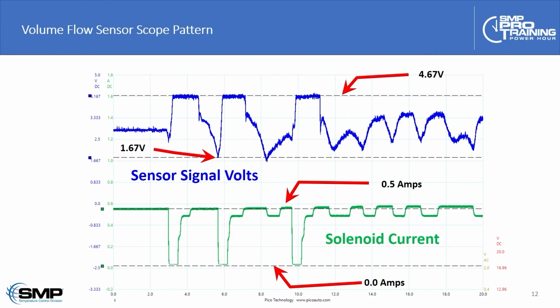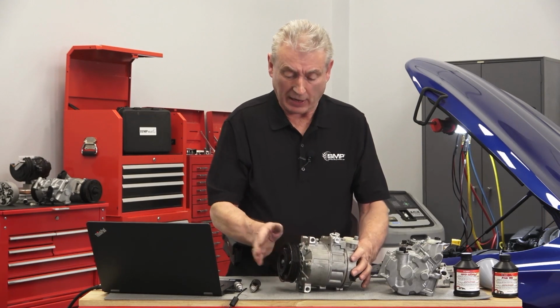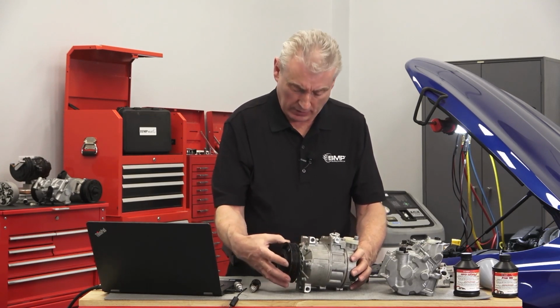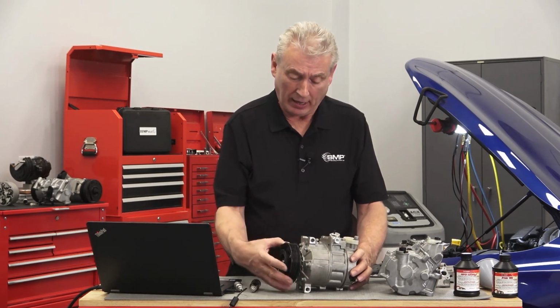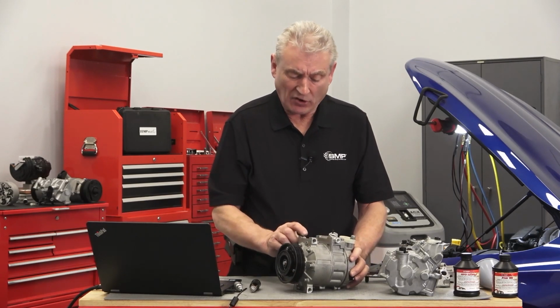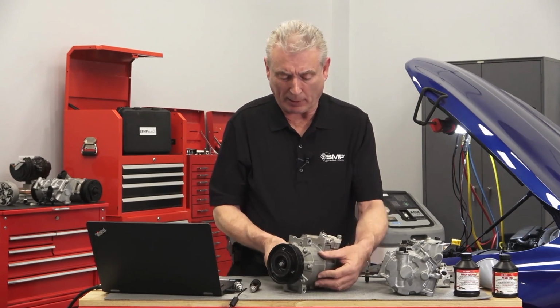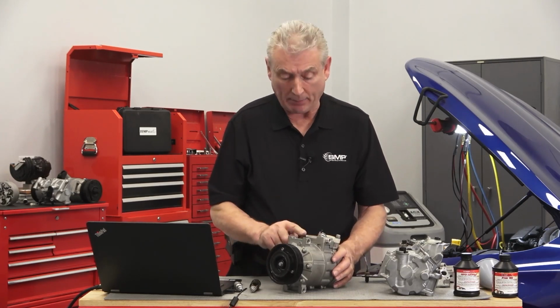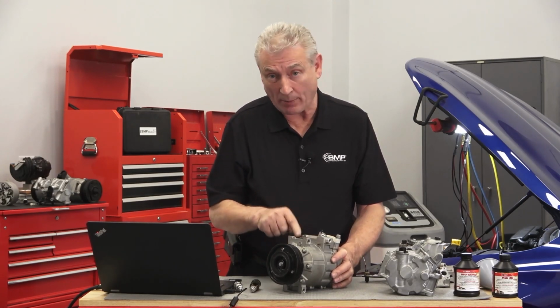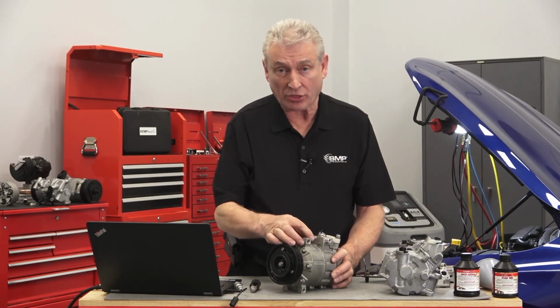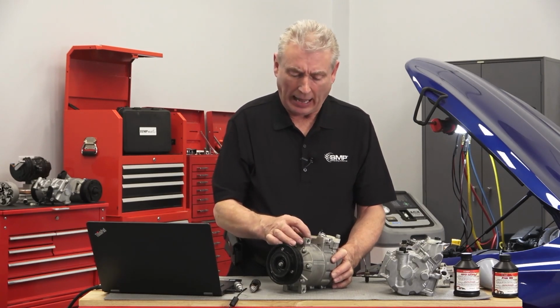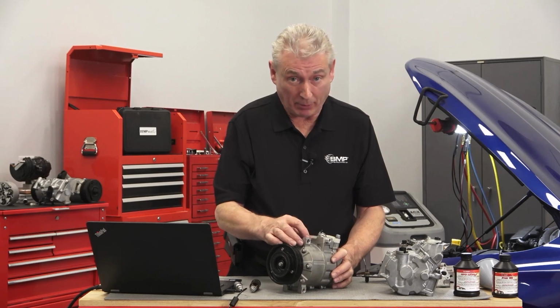So I'm going to grab back my original compressor here, and we're going to share a few diagnostic tips before we move on. As you can see, this is the clutchless version, with the clutchless electronically controlled variable displacement solenoid on board. The first thing is that all these variable displacement compressors have a crankcase. That means if you're draining oil from or adding oil to this compressor, you need to do it through the crankcase drain plug. And this is very important.